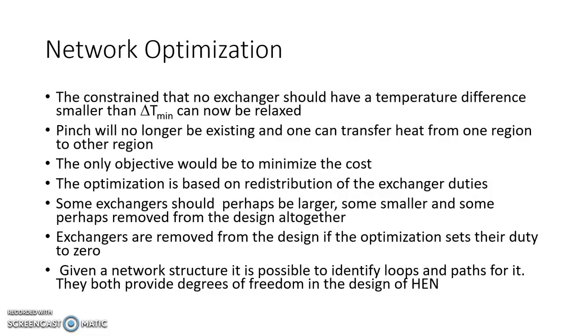The constraint that no exchanger should have a temperature difference smaller than delta T minimum can now be relaxed. The reason for keeping that constraint was that we wanted a tight energy balance and never wanted to go beyond the energy target. Now, from a capital cost perspective, if we relax this for some exchangers, capital cost can decrease and total cost will also decrease. We will maintain the delta T which is practically possible for the given type of heat exchanger.